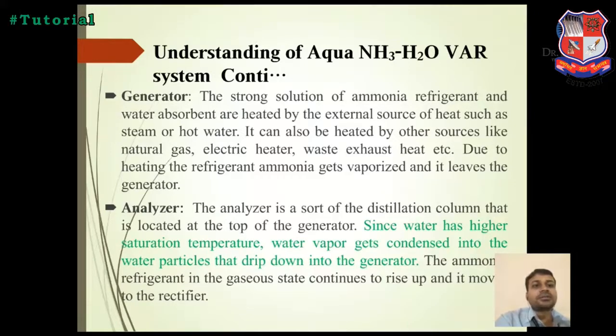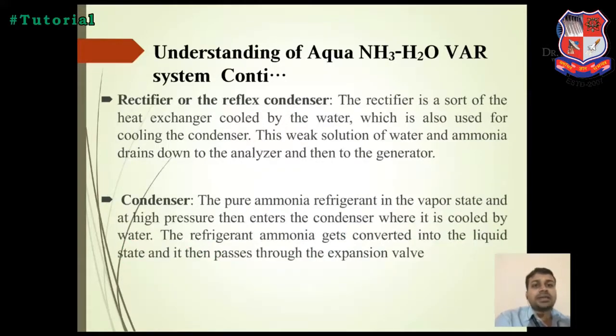Analyzer: the work of the analyzer is to separate the NH3 and water. Water drips down into the generator, and NH3 vapor passes on to the rectifier. The working of the rectifier is a sort of heat exchanger cooled by water, meaning you give a cooling effect by an external source, which is also used for cooling the condenser. This weak solution of water and ammonia drains down to the analyzer, then to the generator. Some H2O remains in the NH3 vapor after the analyzer; a minor amount of H2O is separated in the rectifier and returned to the generator.